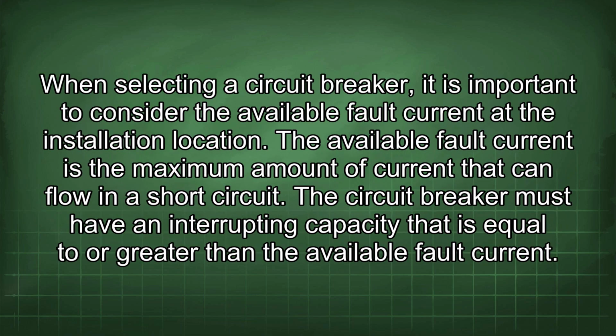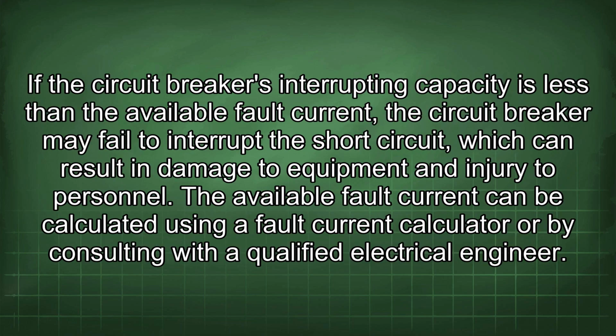When selecting a circuit breaker, it is important to consider the available fault current at the installation location. The available fault current is the maximum amount of current that can flow in a short circuit. The circuit breaker must have an interrupting capacity that is equal to or greater than the available fault current. If the circuit breaker's interrupting capacity is less than the available fault current, the circuit breaker may fail to interrupt the short circuit, which can result in damage to equipment and injury to personnel.